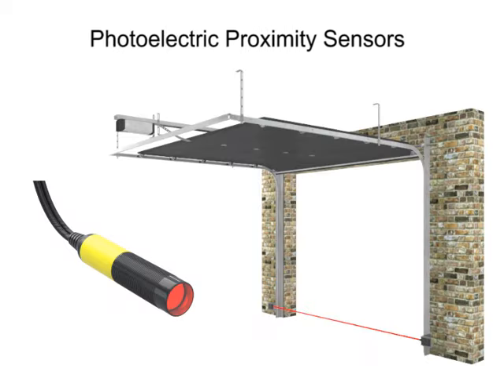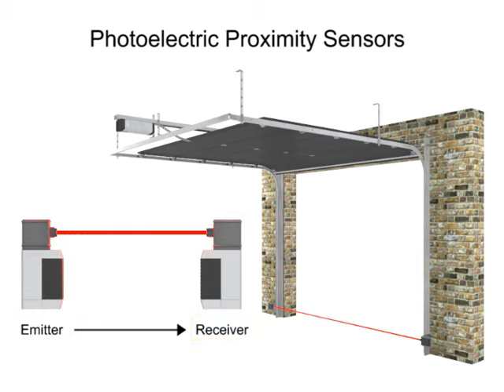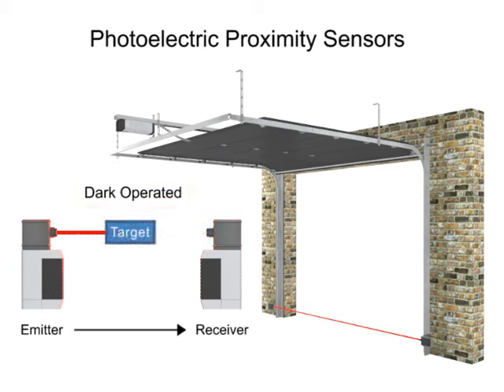Photoelectric sensors have the greatest detection range, from 1 mm to 25 meters or more. They operate by the use of an emitter which transmits a beam of light to the receiver. When the light is normally being received, it is known as light-operated mode. When the absence of light is required, it is known as dark-operated mode.